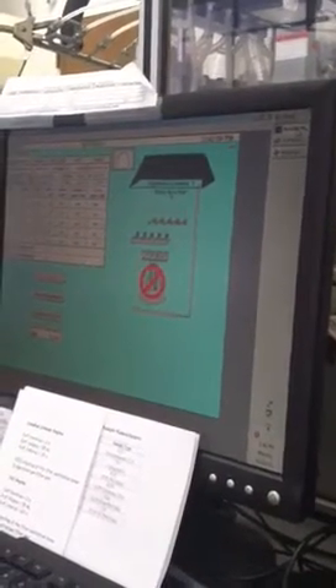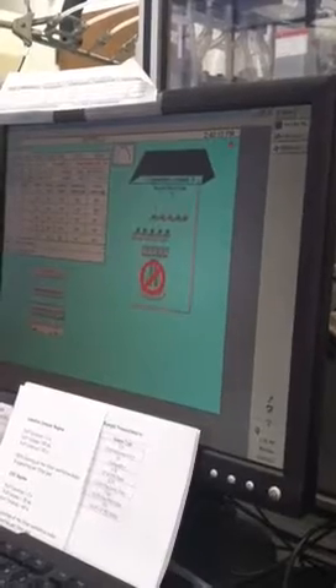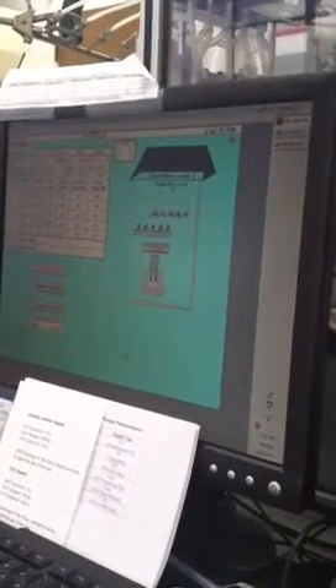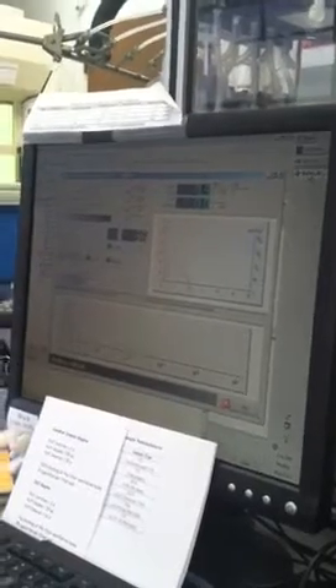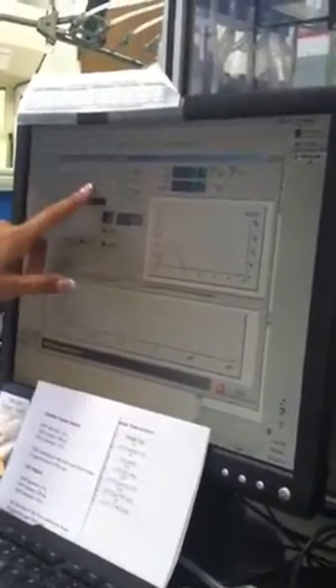Since we have the smoking machine here, I tell it to start smoking. If you're using a fixed volume syringe, this is where you'd actually start. You'll go back here, and oh look, I'm pulling on my pretend syringe, and you can see it. You'll get an average volume, so it's a little bit low. I do this for an average of 10 puffs, and you'll actually get to see it run, and it's kind of boring. Or you pull on your syringe 10 times. Give it enough time so that you're not getting any interference between the puffs, otherwise that will mess with it. So that average volume dropped.